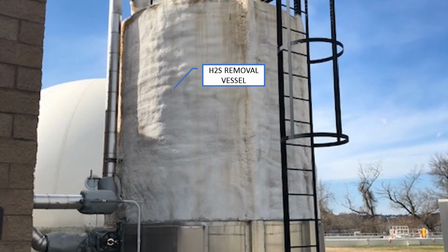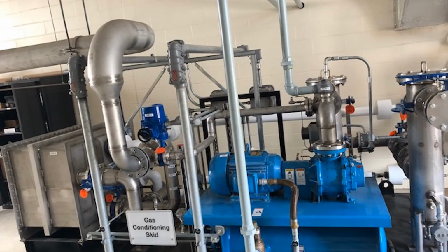Gas that's going to be utilized passes out of the building into an H2S removal vessel. Inside this vessel we have some iron impregnated wood chips that are designed to bring our hydrogen sulfide levels down below 5 parts per million. Once the gas passes through the H2S vessel, it flows back into the building into our gas conditioning skid.